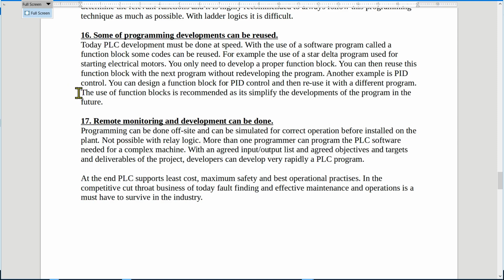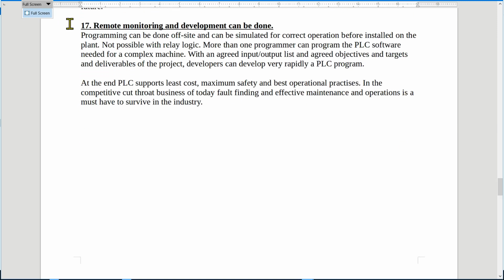Now, if you later start to use Siemens PLCs, then the term function block must not be an obstacle to you. You already met this in Delta, you have experienced it, and you should then be able to understand function blocks in Siemens PLCs. In today's language and in today's use of PLCs, there's a common standard that applies to all PLCs. So if you learn one PLC and you become a master of a PLC, so that you can do analogs, you can do networks, you understand the addressing, you can actually apply this learning that you have done with the Delta PLCs on any other PLC. What is also very important, remote monitoring and development can be done.